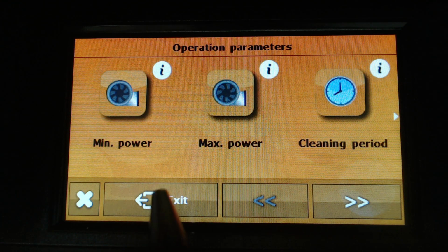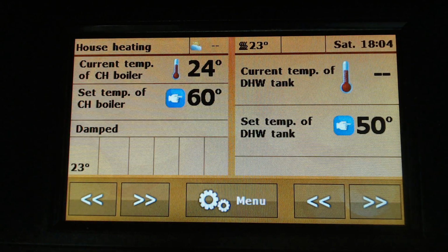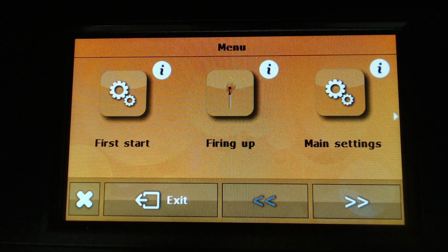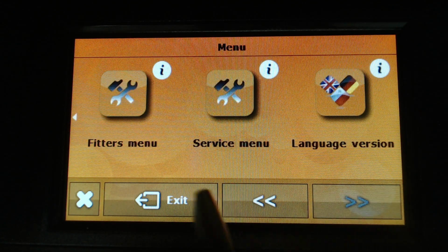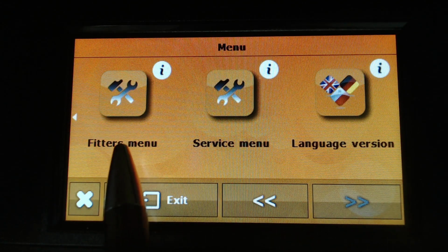And the setup depends on the selection you make during the startup of the boiler, on the power of the boiler you select, and also on the type of the boiler you select. If you want to make sure that the power of the boiler is always spot on, that it is always the power you want, you can always perform feeder calibration in the fitters menu.